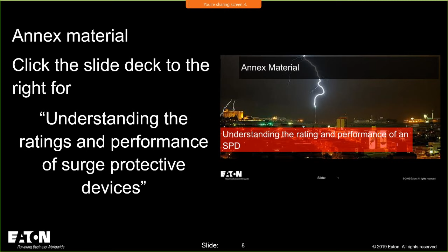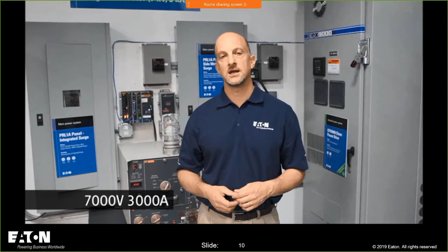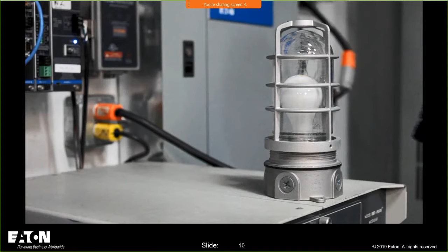So again, what the code's telling us, type 1 and type 2, we're going to be up there at the service equipment. Type 3s are what you'll see at point of use. And then type 4s are really the OEM type of application that you'll see installed in those industrial control panels and whatnot. And then I asked Dan Carnevale to come and give us a couple demonstrations on surge before we closed. Dan? We're going to use a 7,000 volt, 3,000 amp transient to simulate lightning striking near your home or facility. We're going to do this demonstration with a standard incandescent light bulb.